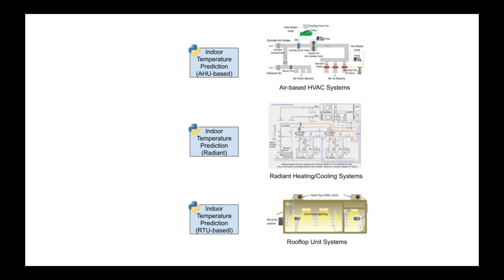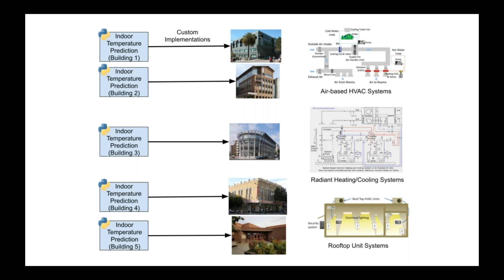But in actuality, when I sit down to write or deploy this code, I end up with a different version of this application for each building. Each building has a custom implementation because its internal systems are constructed entirely differently. They still have the same generic components—air handling units, VAVs—but they'll have custom cooling towers, custom associations of how VAVs and zones are put together, and maybe unusual points feeding back into those VAVs. So we're stuck accounting for all the differences in buildings, which amounts to rewriting the majority of the application's logic every time we deploy it to a new building.